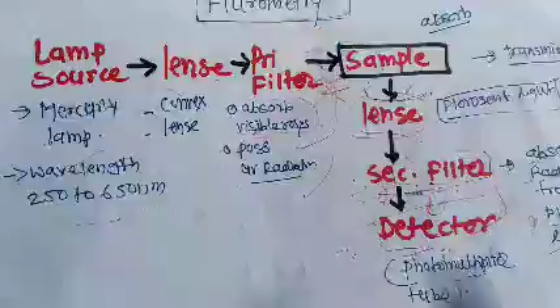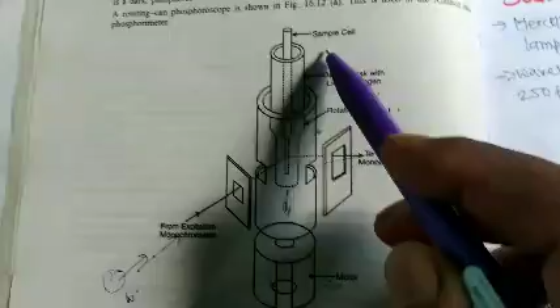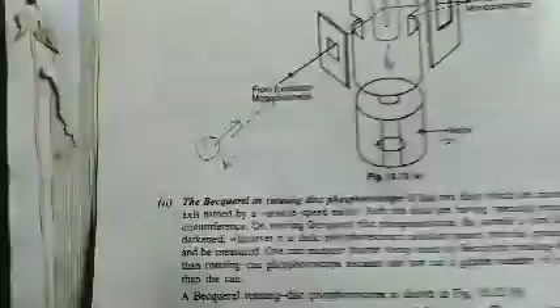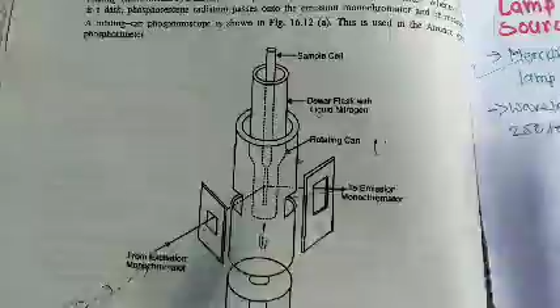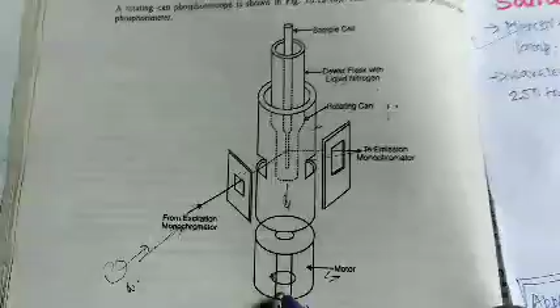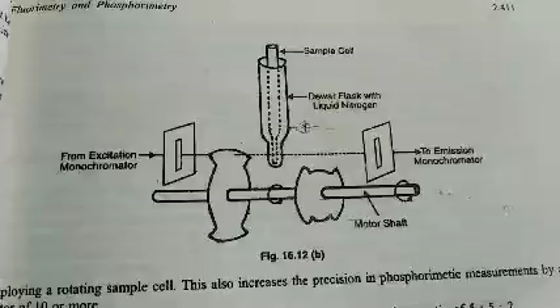So these are all the instrumentation parts and applications of phosphorimetry. Once more in review, here we use mercury lamps, a lens, a primary filter, and this is the sample. In general fluorimetry the sample is fixed, but in phosphorimetry the sample moves in the upward and downward direction. The sample is kept in a Dewar flask which contains liquid nitrogen at a temperature of minus 196 degrees Celsius. The flask moves upward and downward by using this motor. So this is the phosphorimetry instrument and its applications.